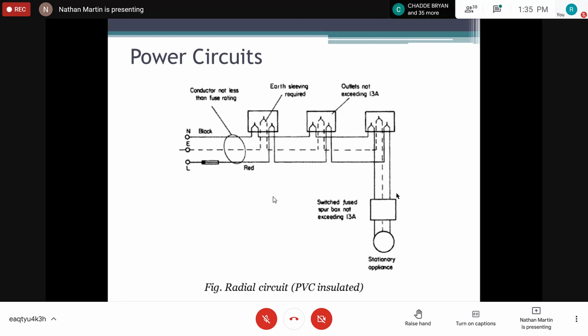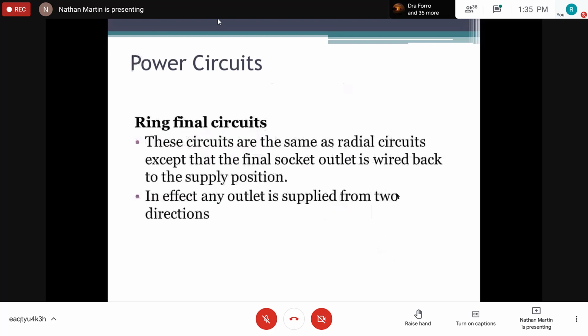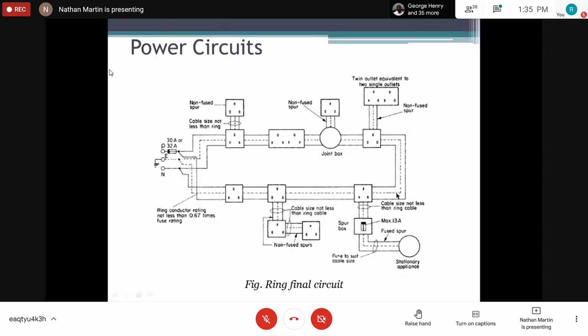However, most installations would be wired like this, rather than having a ring connection. The thing with the ring connection is we are talking about more conduits to feed a particular circuit, because both ends of the circuit must come back to your panel boxes, right? When we talk about our ring final circuit, it's fed from both ends. So this is our ring final circuit. At our distribution point, it is fed in this direction and it is fed in this direction. This is a more stable form of connection.